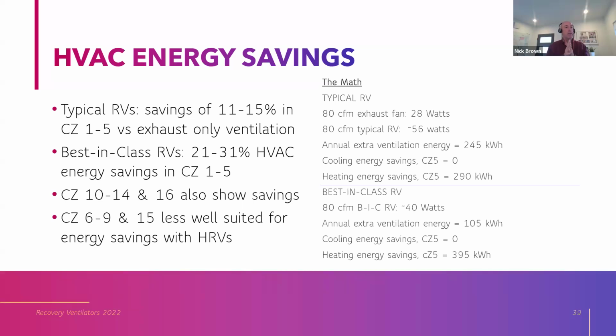Let's say we're in climate zone 5, where many of you probably are, Central Coast. We have no cooling energy to speak of. We're not saving anything there. But during heating season, we're saving 290 kilowatt hours. So that means we just saved 45 kilowatt hours. But notice we used almost all the savings switching from exhaust to balanced ventilation because we have that second fan. And you can think of some climate zones where the heating and cooling savings might not outweigh the extra ventilation energy, right? That's the trade-off.